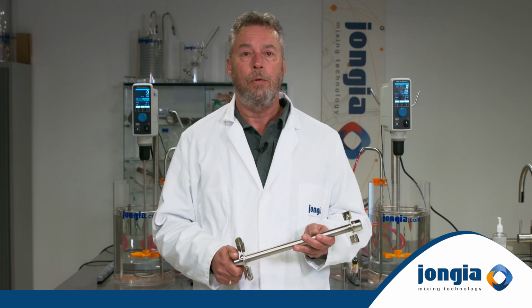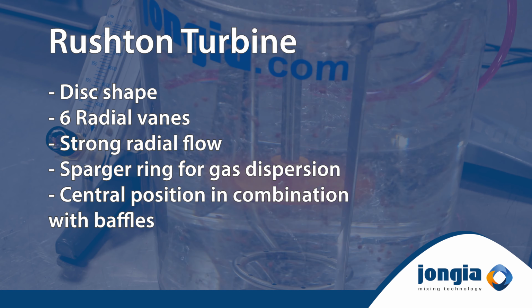The turbine has the shape of a disc with 6 radial vanes. These vanes create a strong radial flow. Such turbines are often used in combination with a sparging ring to distribute the gas evenly under the turbine. Due to the high shear generated by the shape and high RPM of the turbine, such turbine configurations are mostly located centrally in combination with baffles.